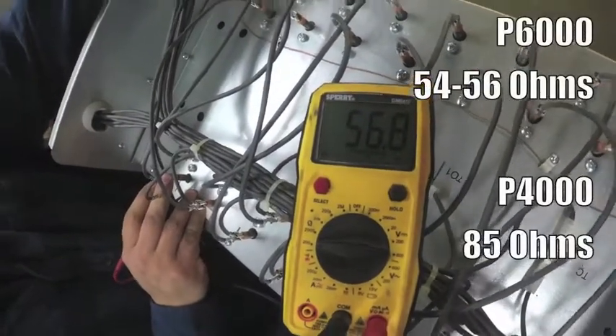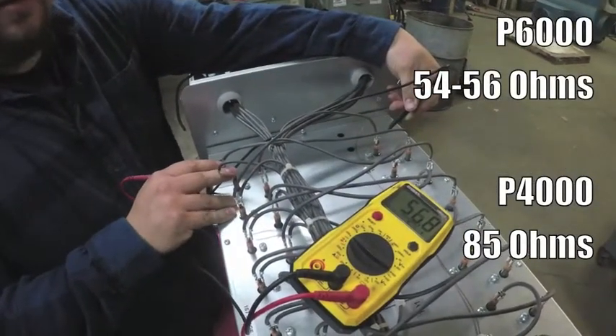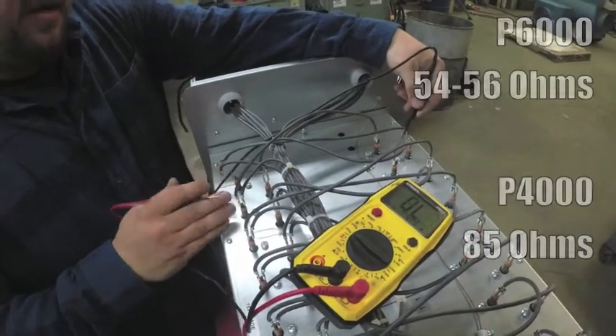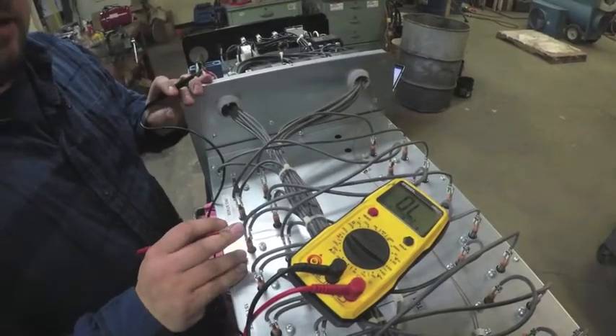Generally, you're going to be around in the 54 to 56 range ohms for a P6000. P4000s, you will see 85 ohms. This applies to every coil in this unit. Remember that you do need to test each coil individually.